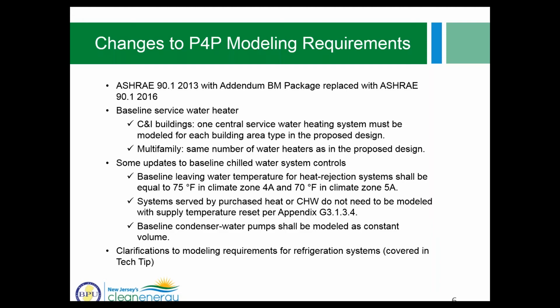So on this slide, I highlighted a few examples of where rules have changed, and perhaps the most significant and impactful change is in respect to the baseline service water heater, and this is the service water heater that you would model in the baseline model. So for all buildings except for multifamily, the program follows Appendix G rules, where baseline must include one central service water heating system for each building area type in the proposed design. That means that if you have a mixed-use building, say part of the building is office, and then there are a couple floors of retail space on the lower floors, you would have two central service water heating systems modeled in the baseline, one serving office floors, another serving retail.